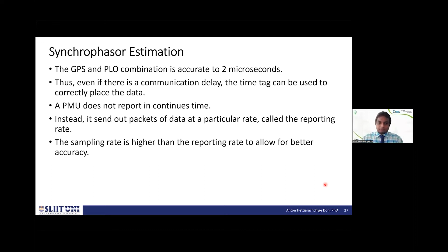So what it does is take a large number of samples within the reporting rate. If you say 30 times a second, to achieve that, at every 1/30th of that time, it takes multiple samples and combines them through complex algorithms that you'll learn about later in the workshop. It does mathematical calculations and sends out a signal, doing that 30 times every second. So it takes multiple measurements, combines them, puts a time tag on them, and sends it out - 30 times every second, or even 60 or 120 times with newer systems.